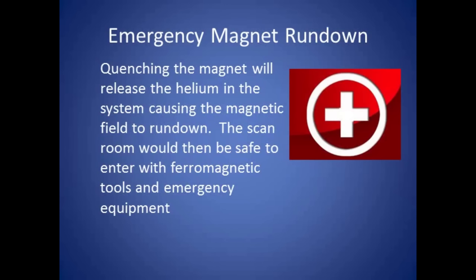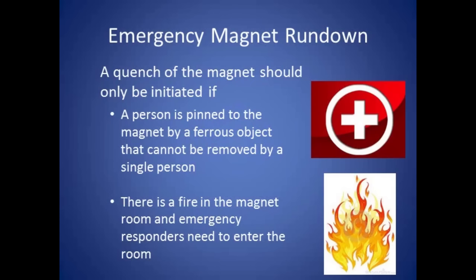A quench of the magnet should only be initiated if a person is pinned to the magnet by a ferrous object that cannot be removed by a single person, or if there is a fire in the magnet room and emergency responders need to enter that room.